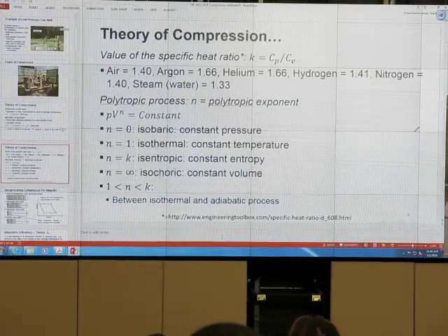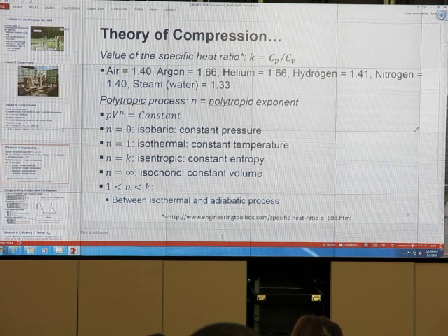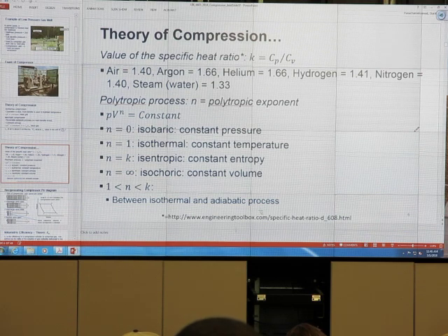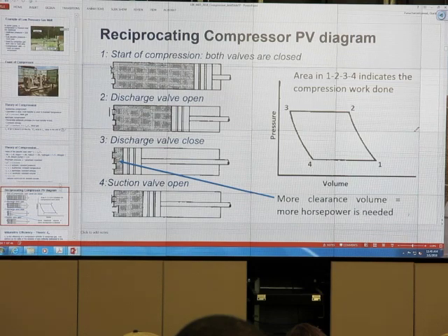So I start with 0 psig, and I want to compress my gas from 0 psig to 30 psig. William, what is the compression ratio? How much? 1, 2, 3, 4, 5. 3. I think that's about right? You convert it to psia, so 30 plus 14.7, divided by 14.7. So that could be about 3. That kind of thing you should know.